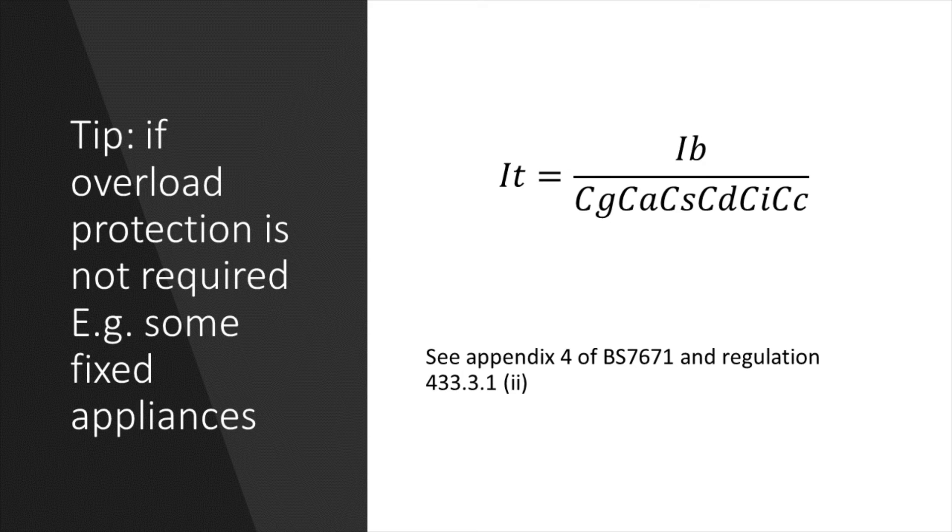However, in this situation the protective device must provide protection against fault current. So it's very important to carry out both adiabatic equations. And that's what the regulation means when it refers to section 434.